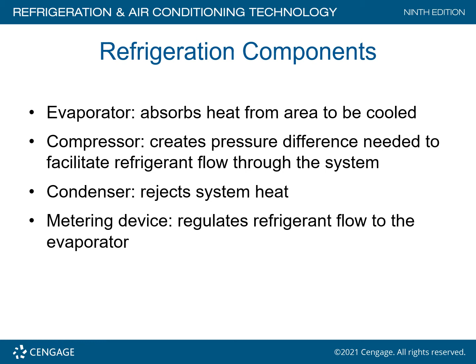The metering device can be a capillary tube, a piston, a thermal expansion valve, or an electronic expansion valve. It regulates the refrigerant flow to the evaporator. On the newer systems, I utilize, as an example, a Fieldpiece 360 or 460 digital manifold set, which we have in the lab. What we're going to observe when the system is being charged or checked is that the expansion valve in this case is going to open and close. We're actually going to be able to see that based on the superheat and subcooling and the pressures on the system. We'll see those increase and decrease, telling us as service techs that this system is working properly.